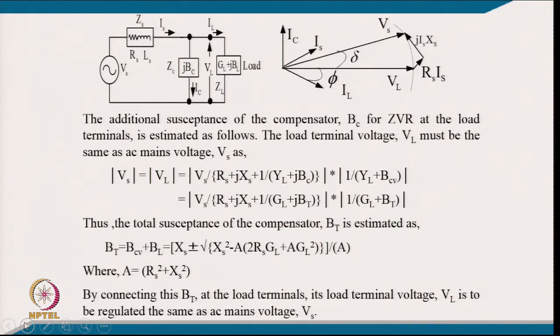That is the reason we go for this, and in substations we really use capacitor panels. Now the phasor diagram corresponding to 0 voltage regulation, which we already discussed earlier: you are putting a compensator in parallel with the load, and we consider VL equal to VS. If we put a compensator current a little higher, not only equivalent to the load, but compensating in a manner that the IS and RS drop, we draw a circle with the radius of VL over the center point, and virtually this drop, with IS, will come to lie on this circle.